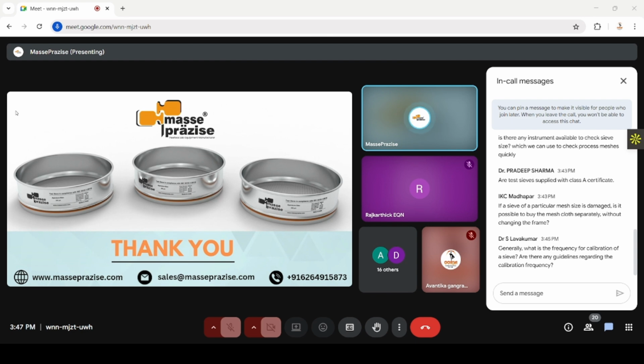If a sieve of a particular mesh size is damaged, is it possible to buy the mesh cloth separately without changing the frame? Yeah, this is possible, but it depends on the manufacturer, because whether the mesh will fit in that particular frame size has to be checked. So you can contact the direct manufacturer whose sieve you are using, or if you want us to change that mesh, then we have to verify. Once we check the frame, we have to verify whether our assembly is able to fit in that or not. Then only can we clear that point, whether we can replace it or not. So it is important to physically see the frame to repair it, if it is repairable. As I discussed earlier, there are two types of frames: one is repairable, and there are some unibody meshes that cannot be repaired.